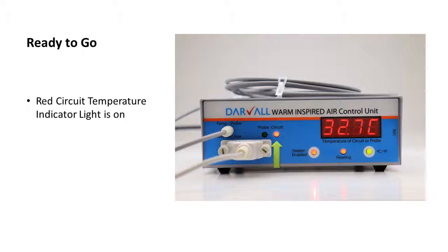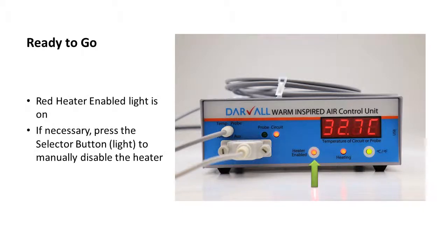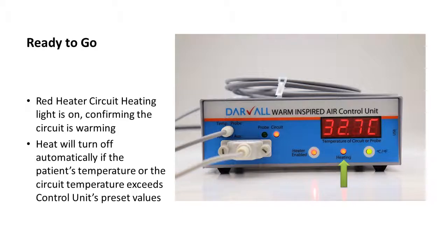The red circuit light and the green probe light toggle back and forth automatically. The red heater-enabled indicator light is also on. Although the heater will disable automatically if the patient's temperature or the circuit temperature exceeds the control unit's preset values, the heater-enabled selector allows you to disable the heater manually by pressing the selector button. The red circuit heating indicator light is on, indicating that the breathing circuit is warming. The heat will turn off, and this light will go out automatically if the patient's temperature or the circuit temperature exceeds the control unit's preset values.